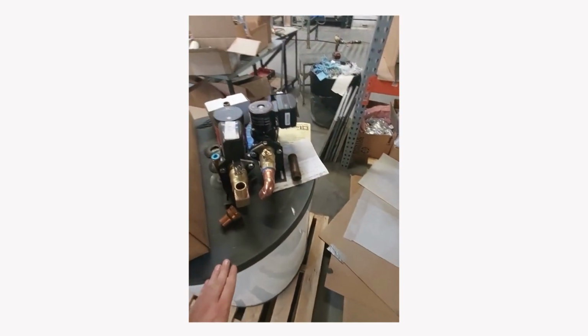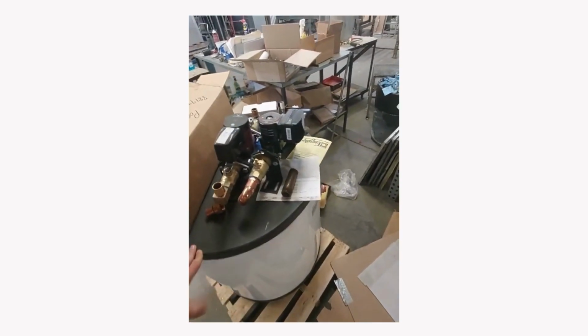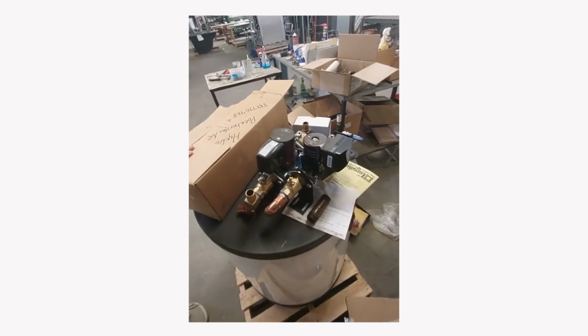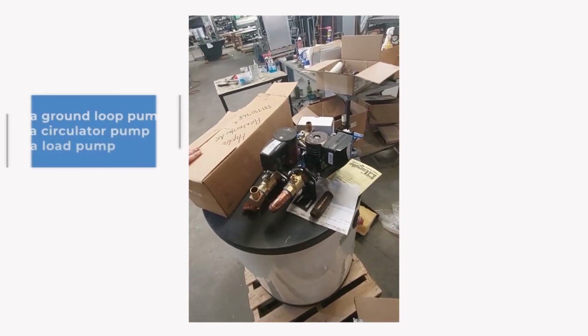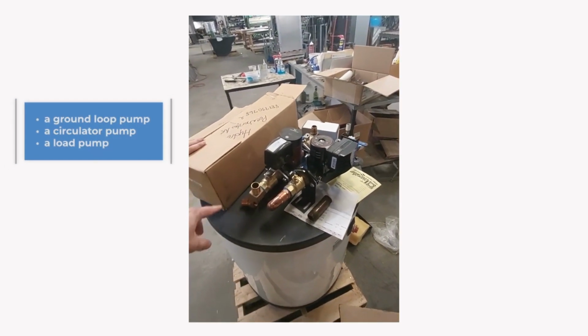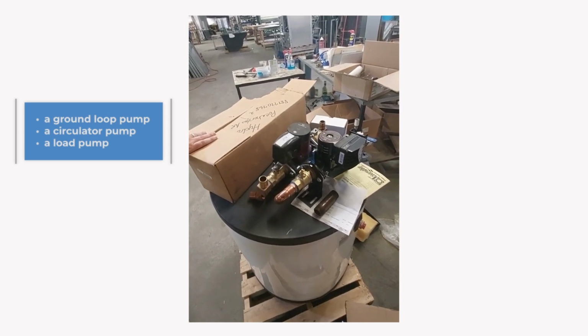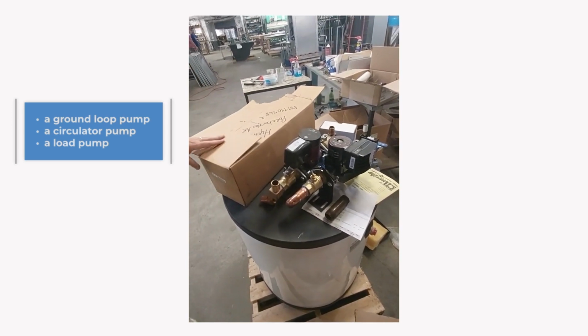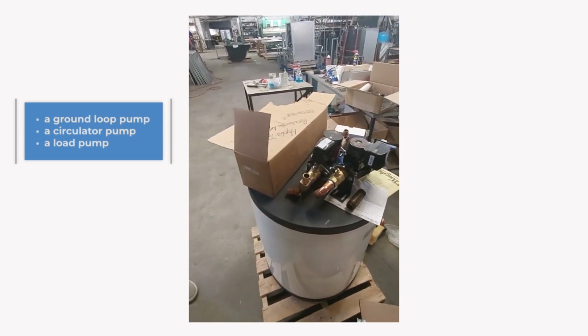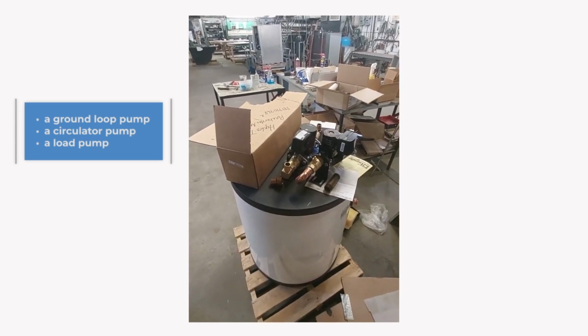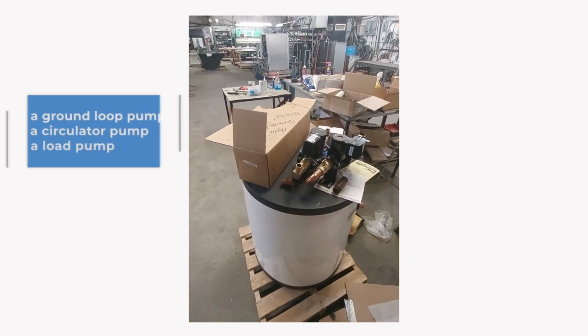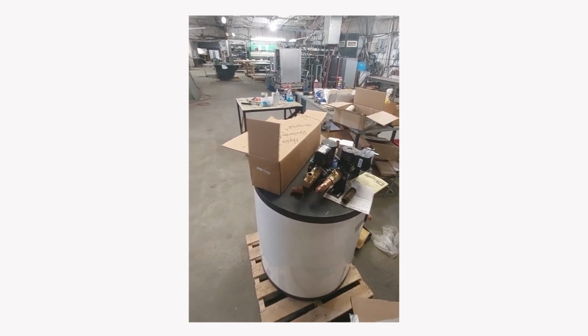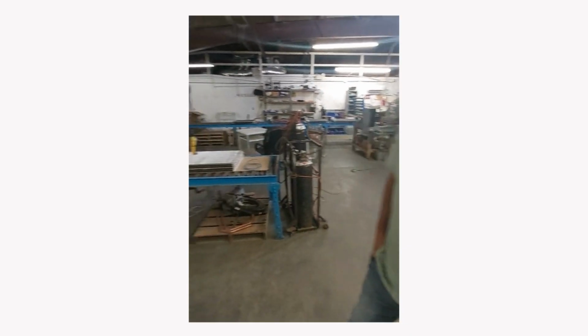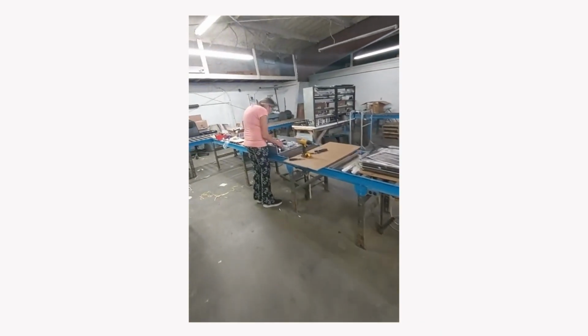This is a 65-gallon tank, and our heat pumps also come with 3 pumps: a ground loop pump, a circulator pump between the tank and the heat pump itself, and a load pump to actually deliver that hot water to the building in the case you're using it for hot water heating. All of that comes standard with our unit, and we're going to show you that in a second. So let's keep going along this way to the electrical if we can.